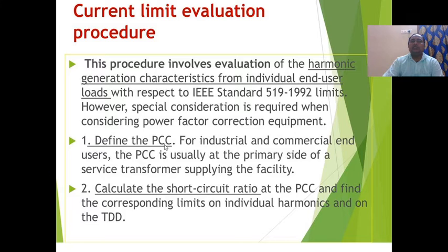Define the PCC. What is the PCC? Point of common coupling. For industrial and commercial end users, the PCC is usually at the primary side of a service transformer supplying the facility. Second one, calculate the short circuit ratio at the PCC and find the corresponding limits on the individual harmonics and on the total demand distortion.